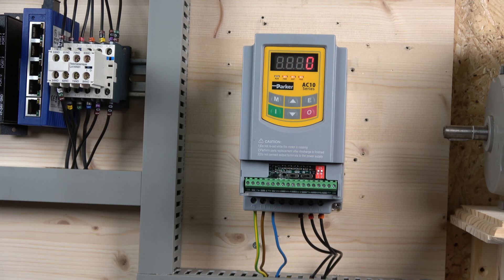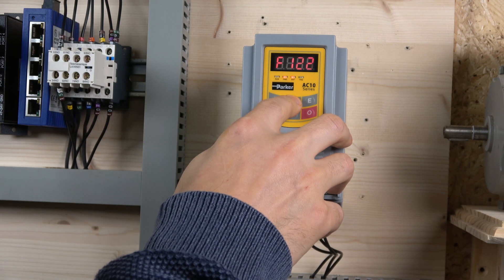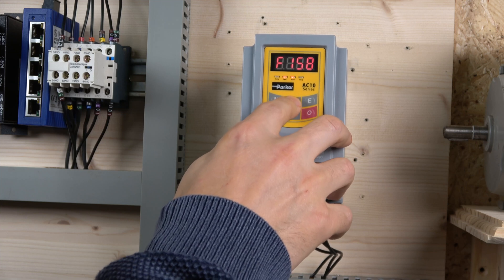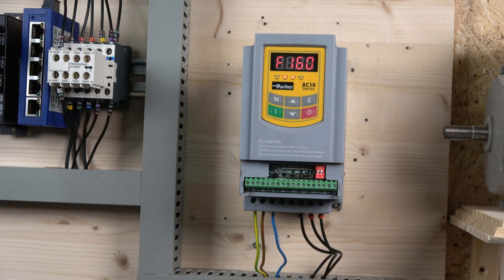The next thing we need to do is perform a factory reset. To do a factory reset, go to parameter 160, change it to 1, and press enter. The drive will revert all changed parameters back to factory defaults — it returns to F100 once done. That's how you reset the AC10 series drive.